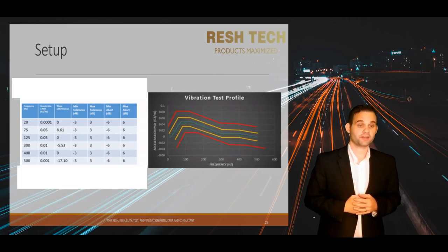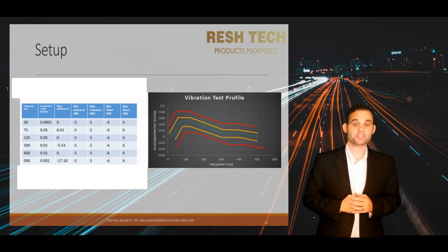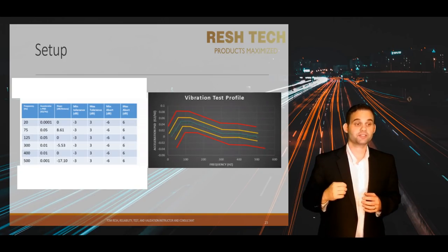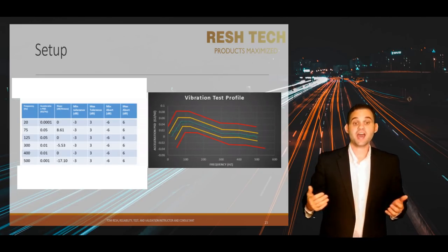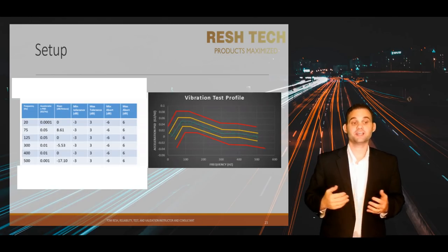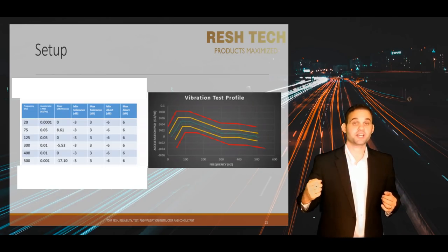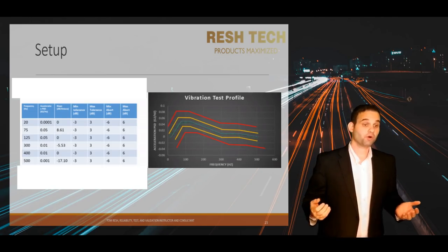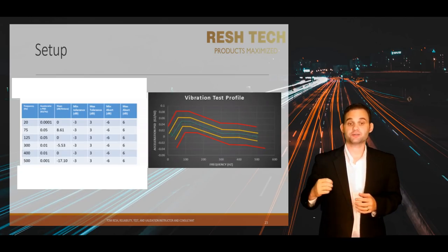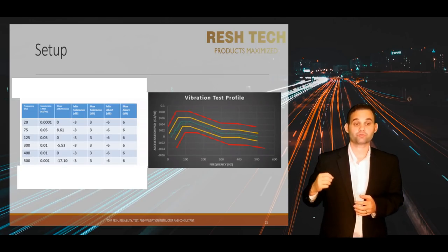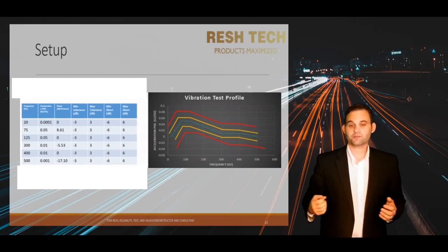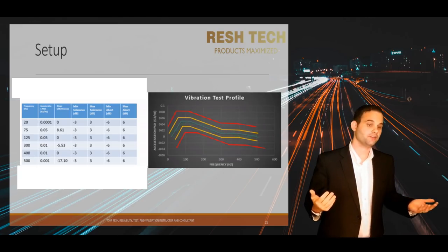The abort limits, on the other hand, are something everyone should care about. Typically these are set to -6 dB and +6 dB respectively, and you should leave these alone unless there is some very rare case requiring you to change them. The abort limits are there to protect your system or product if you have a setup issue that could cause acceleration levels to run much higher. So do not mess around with these values unless you need to and know what you're doing.